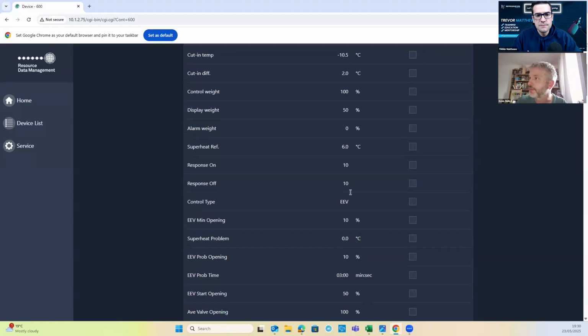You've then got your EEV settings, because it's an EEV controller. You can set your superheat reference in there. 6 is a good starting place, as we know. If you need to turn it colder, or you need to turn it warmer, you can do it from there. Response on and response off is how fast the controller responds to the superheat changing. So when I first do a case or a cold store, I'm not changing those. I'm going to see how it runs.